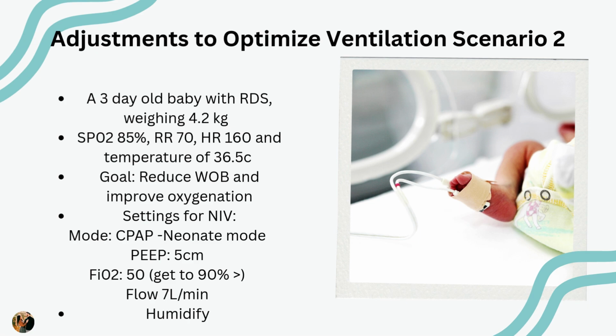And a great thing with these is that we have a neonate mode. So this is wonderful for babies. So we would select that. And we're also going to want to keep our PEEP around 5 centimeters and our FiO2 at 50. Just like the case before, we don't want to go too high, but around 50 is a good starting range. And we want to see that SpO2 get upwards of 90% or more. And we also want the flow around 7 liters per minute, I would say.